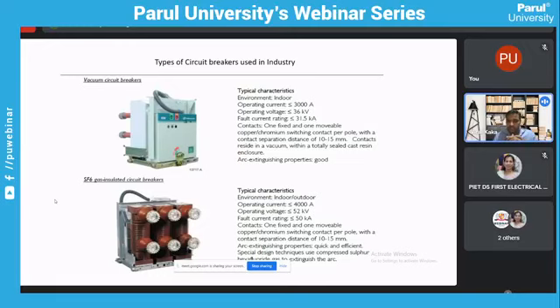Below is just shown as another detail in terms of gas insulated switchgears. The major advantage of using a GIS compared with air insulated switchgears, which in a way both have a vacuum interrupting bottle, is that the fundamental difference is the vacuum interrupter in gas insulated switchgear is inside a gas tank. So the footprint of the overall switchgear reduces drastically, at least by 30 to 40%. If we go with gas insulated switchgear, that gives a good bit of floor space saving in substations, as well as in areas where we are seeing a shortfall in spacing.